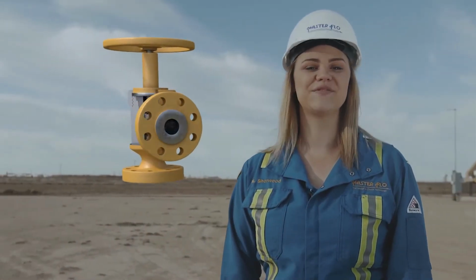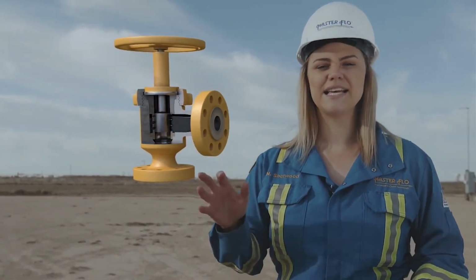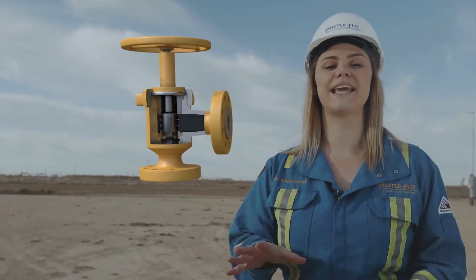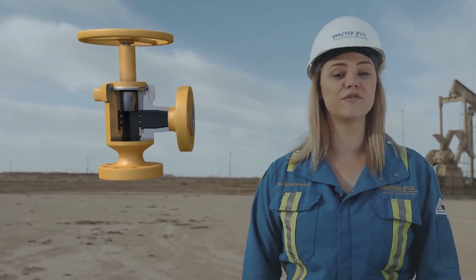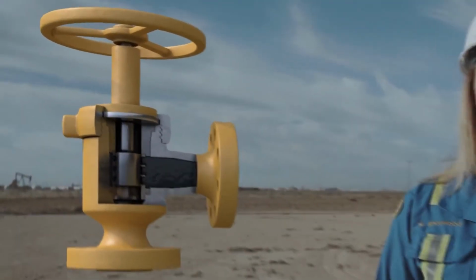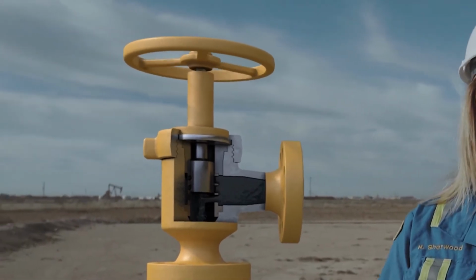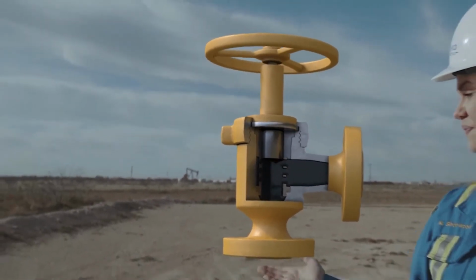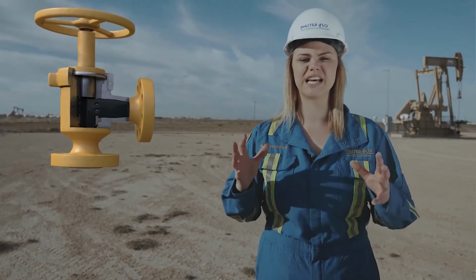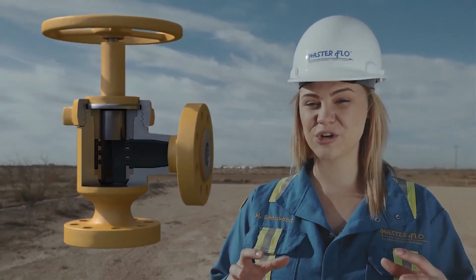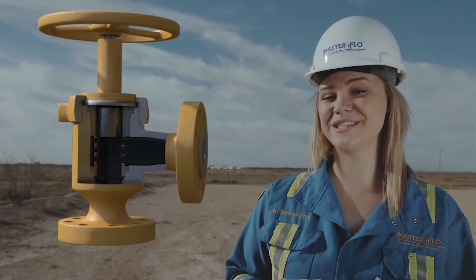Our next choke valve has fixed cage and internal plug. A stem connected to the plug allows the plug to be moved up and down by the rotation of the wheel, changing the size of the opening for the flow. Inside the choke, fluid circulates in the annulus between the body and the cage. The location of the cage openings forces the streams to collide in the middle. Impinging streams cause hydrostatic back pressure and allow using fluid energy against itself, resulting in minimal wear of valve material.